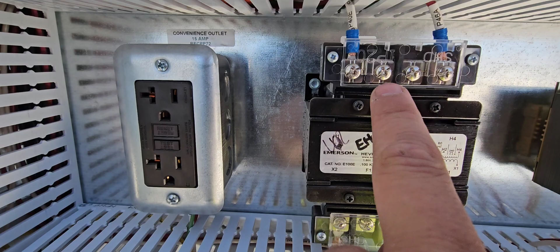But depending on where you were to tap that, it will affect your voltage on your secondary side. So like this, we got 120 and 240 coming in, which granted, since this is landed 240, I think if you were to land at 120, you might mess up this transformer. But especially on ones like this, if you're getting 208 power but you have it tapped on 240, you're gonna affect your secondary side, okay.